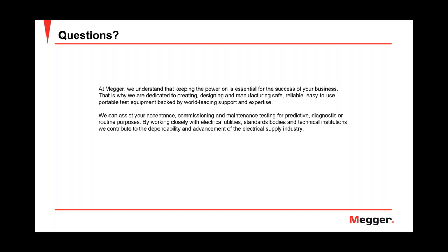Do you see any issues with introducing voltage for an arc reflection test through a transformer or through a series of transformers? Initially, the answer to that is no, but we have to understand what we're doing whenever we do an arc reflection. As Glenn pointed out in this presentation, initially you're going to do that first low voltage TDR trace, which is a low voltage, high frequency pulse. And then you're going to follow that with the high voltage, high frequency pulse of the arc reflection. Both of these will be sent in to the primary coil of the transformer.